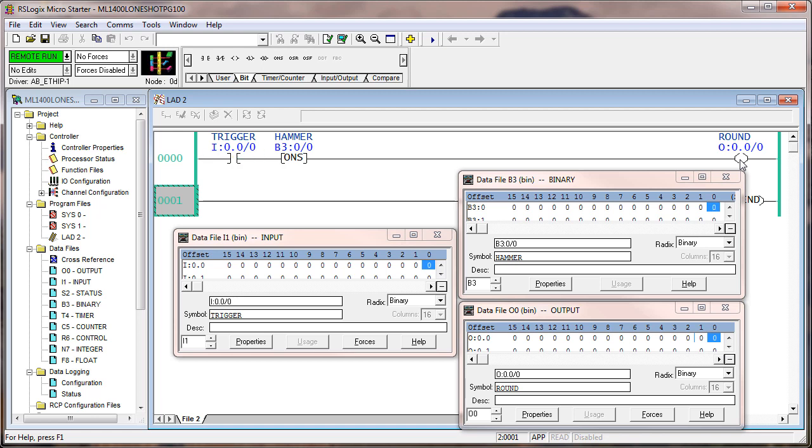So how could you prove that that output was actually going on every time this instruction went from false to true? Now remember, this instruction represents everything between the left power rail and the one-shot instruction. This could be a dozen instructions. And when they're all true, that's the same as this one instruction being true. That's what we're demonstrating here: we have really three areas of interest. Whatever is to the left of the one-shot, whatever is to the right, and the one-shot itself. What it's actually executing really is of no importance to us. We're only talking about the one-shot instruction.